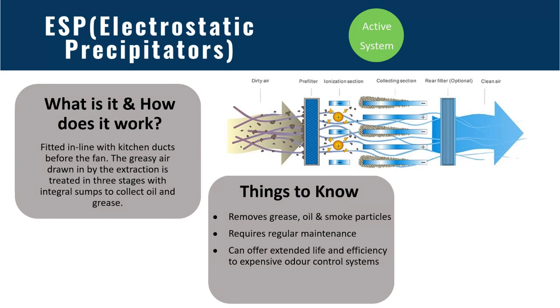They draw the extracted air and then treat it in 3 stages with integral sumps to collect the oil, grease and smoke particles. The first stage is a metal washable air filter that removes large dust and grease particles in the airstream. In the second stage, smaller grease and smoke particles pass into a strong electrical field where they become charged. In the third stage, the charged particles pass through collector plates that are designed to attract and collect the smaller particles, resulting in clean air.